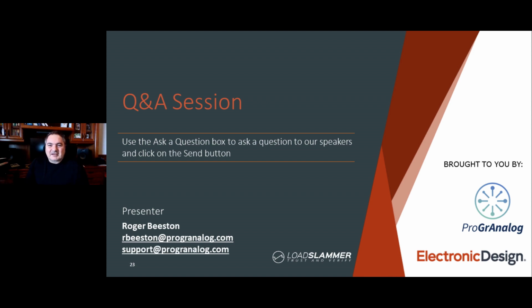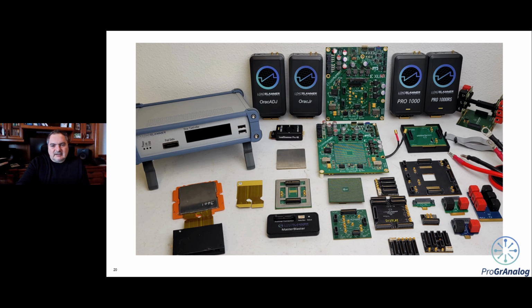For the next one here, could you explain the DC load connection again? Yeah. Can I change slides? Is that okay to do that? Sure. In this example, with a passive solution, you connect what we call a PTO, power takeoff unit, and that plugs into the large Samtec connection, and you can connect that to an E-load. That's what you do with a passive solution. If you have an active solution, you just turn up the DC load that you want, and it dissipates it through the active load cells.